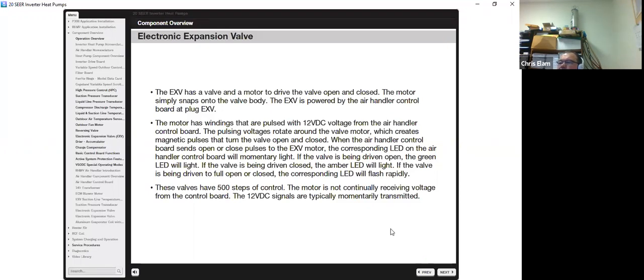These valves have 500 steps. In the control board, you'll see an option for a 1600 EEV motor, which is not being utilized yet and may not be for some time. So these current motors have 500 steps. If you change it to 1600 by turning the dip switch on, you're going to have some serious erratic operation. 12-volt DC signals are usually momentarily transmitted, so you can actually keep your eye on if it's on or off.